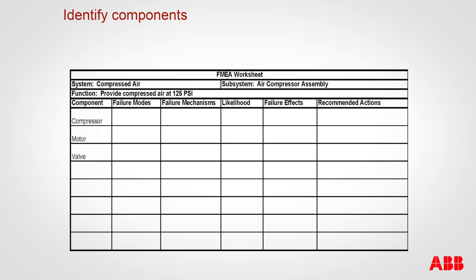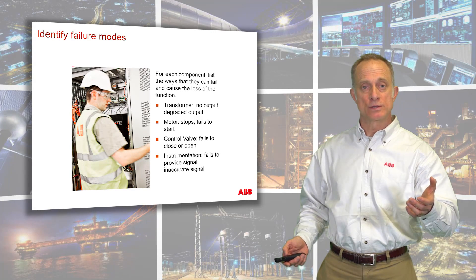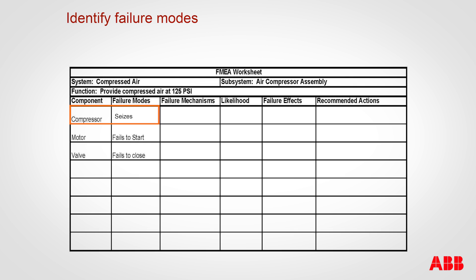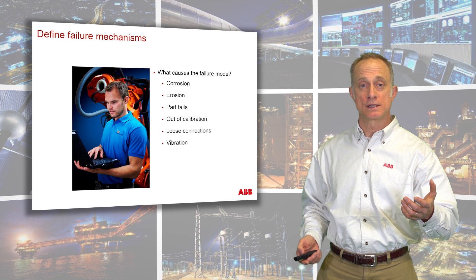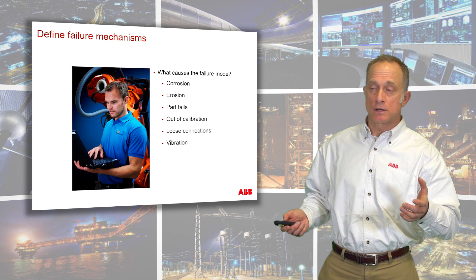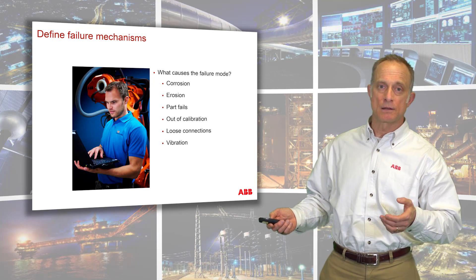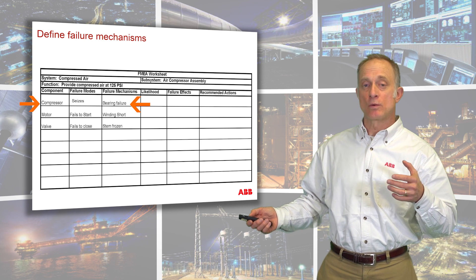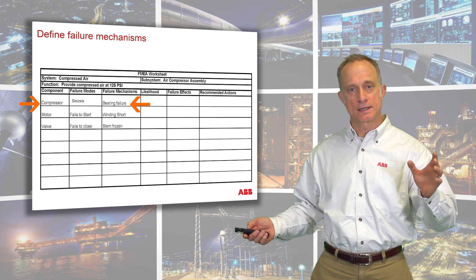In our failure modes and effects analysis worksheet, we'd have the compressed air system looking at the subsystem of air compressor assembly, and the components would be compressor, motor, and valve. We then want to identify the failure modes — what could go wrong with each of those components? For a compressor it might seize; for a motor it might fail to start; a valve might fail to close. Next, we look at the failure mechanisms — what would cause these things to fail? It could be corrosion, erosion, a part failure, or improper calibration. For a compressor, the failure mode is that it seizes, and what would cause that might be a bearing failure. So we go through all of our systems like that and fill out this sheet.